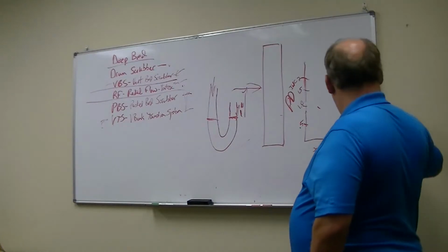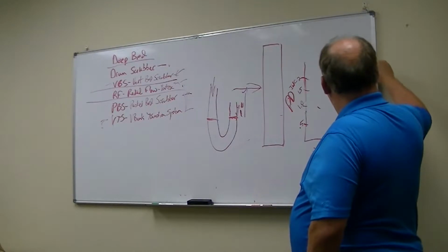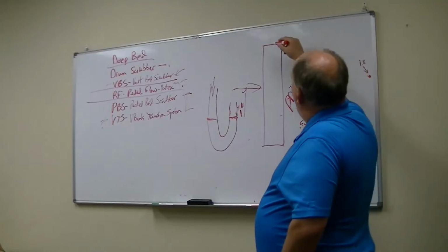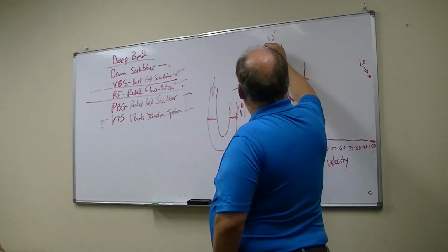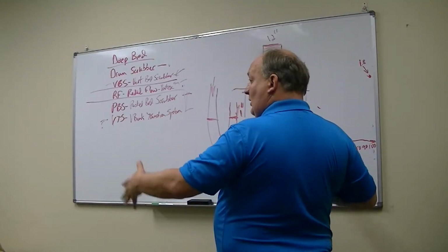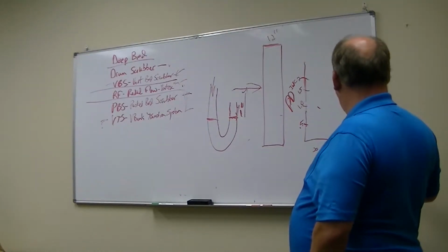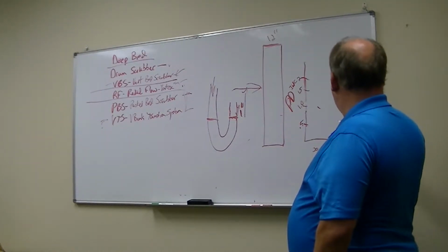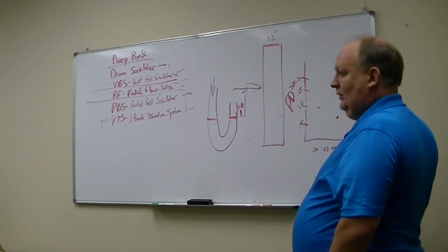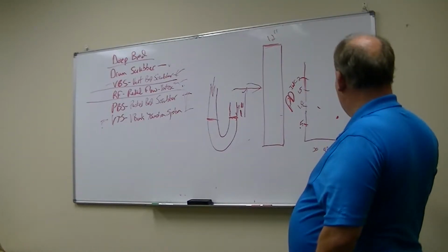So at 100 feet per minute, the number that we typically use is 1.8, okay? And that's for a 12-inch deep bed, because you remember, you may have a 12-inch bed, you may have a 24-inch bed, you may have a 36-inch bed, okay? So that's the point there. And then for 50 feet per minute, it's something like 0.6, I think, or so. We're not real good on having real good published numbers on that stuff, I tell you.